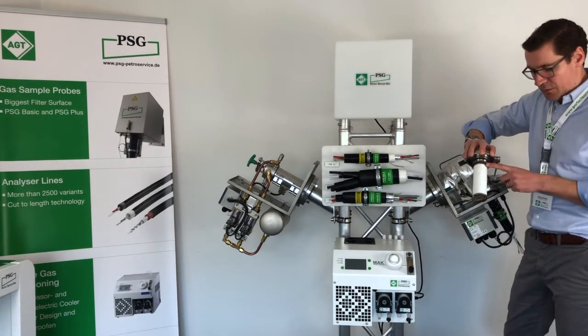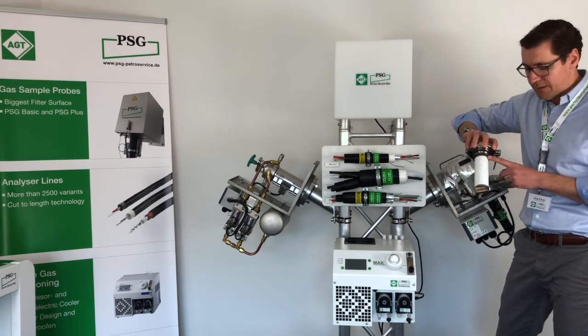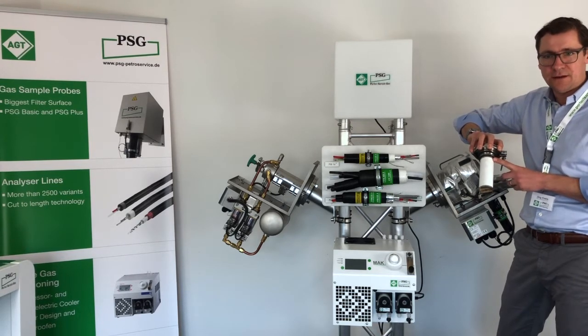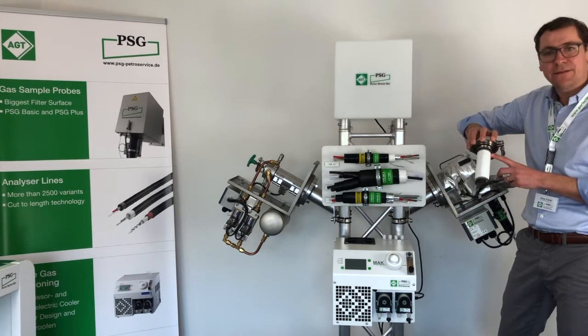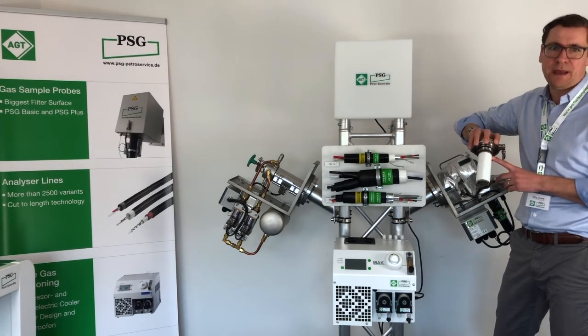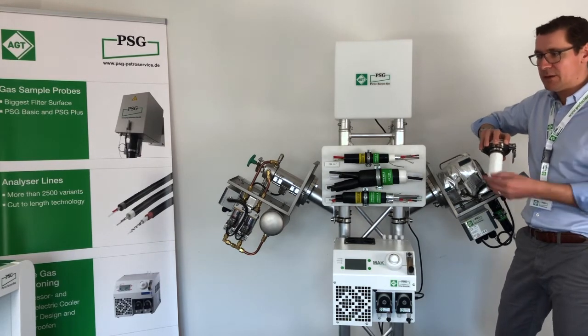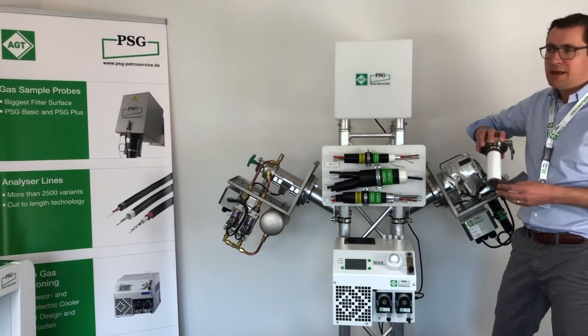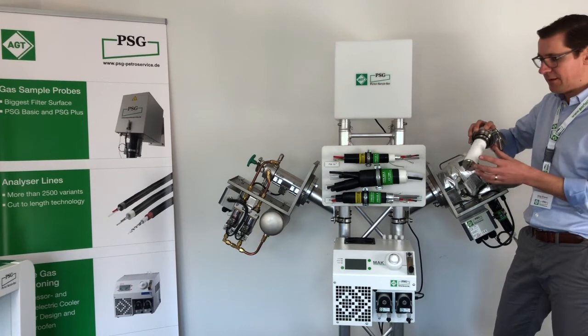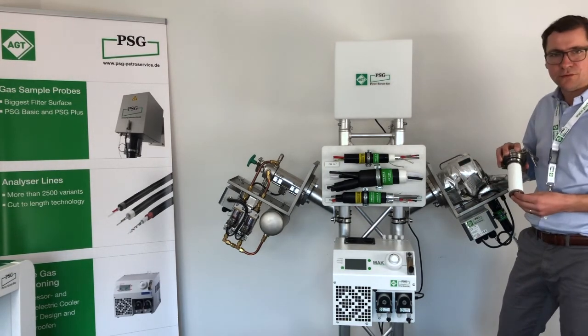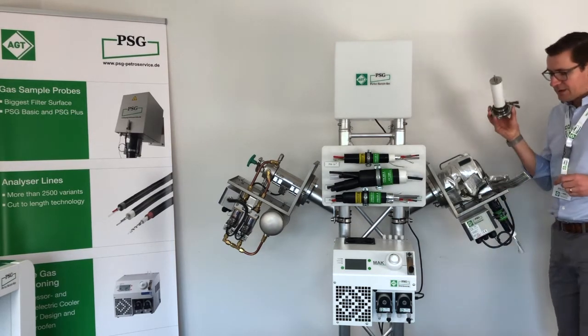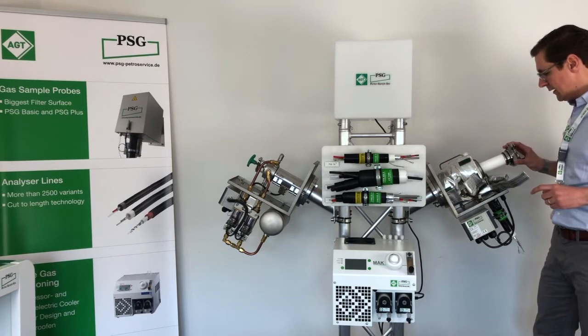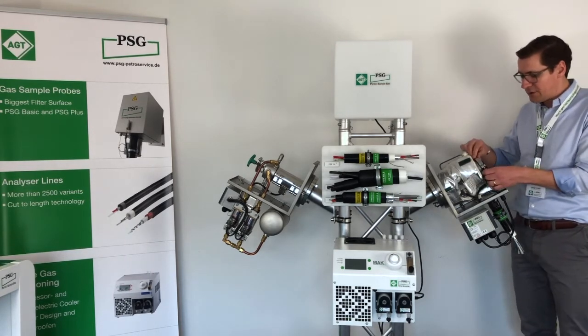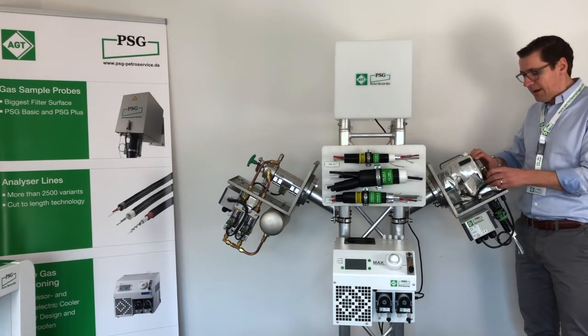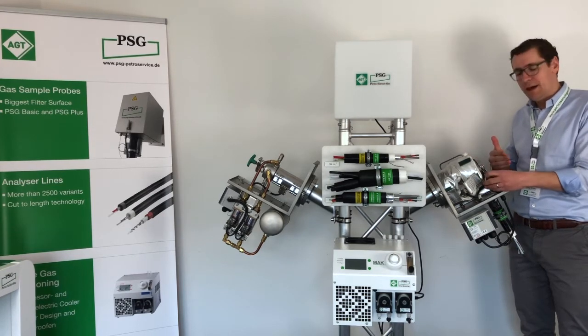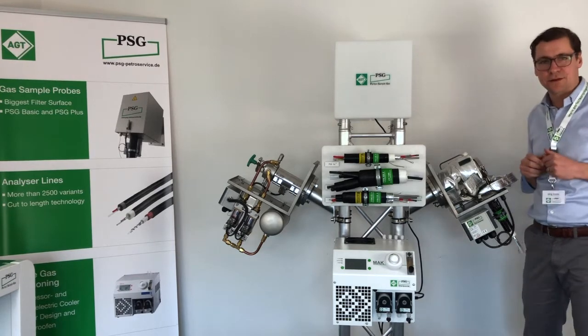As you can see here, we in AGT-PSG use different filter material, which you can find in the data sheet of our description. Here you can see the glass fiber filter, which is a standard for the PSG basic probe. If your application requires a ceramic filter, obviously this is also available, and you can exchange. So the filters are compatible between the two different products. Next to the easy exchange of the filter and the very compact flange clamp, it allows to have a very compact probe, but still to have the biggest filter surface size in the market.